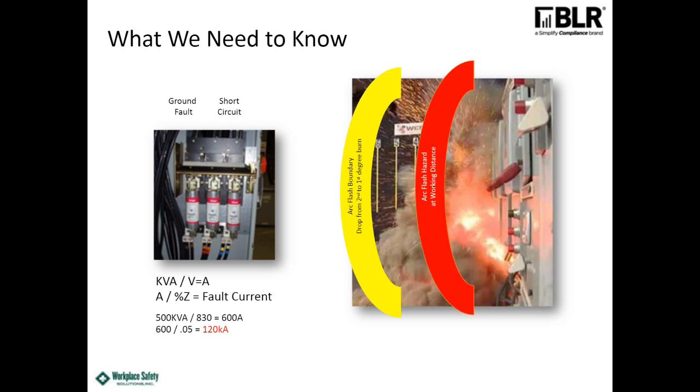On the outside of the boundary, you could have cotton clothing, natural fiber clothes, that kind of thing, and not have to wear a shield because you only maybe have a first-degree burn if it were to happen. So that's an important boundary to know, and that's on the engineering labels that would be done to tell you what that is. So what causes it?